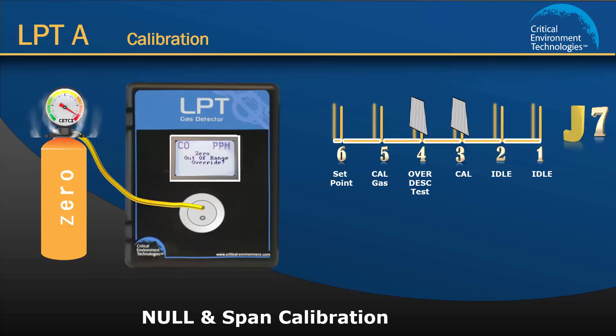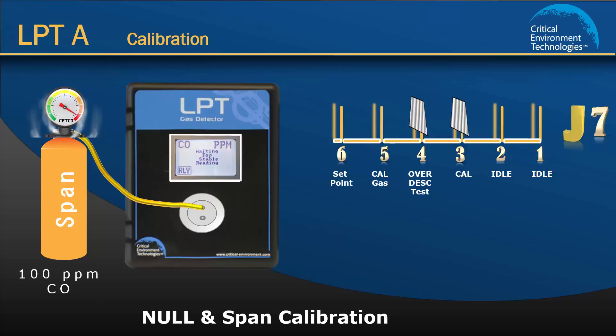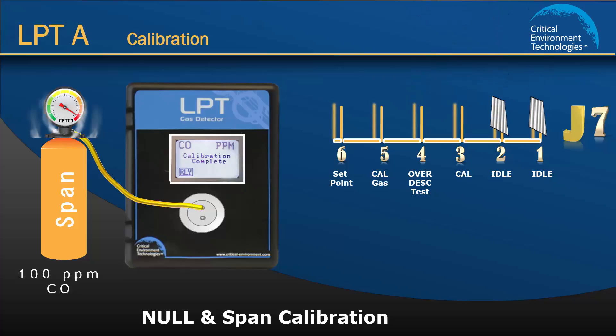When the message flow gas appears, attach the span gas cylinder and open the regulator valve fully to allow the span gas to flow over the sensor. When the gas flow is detected, the display will read waiting for stable reading. After the span is successfully completed, the display will show calibration complete. Return both jumpers to their idle position and the LPTA will return to normal operation.